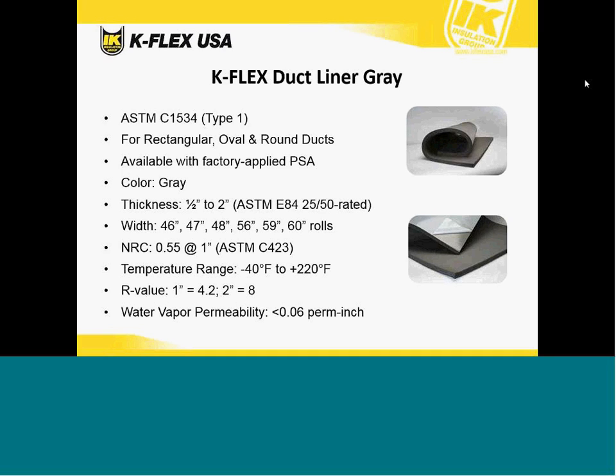The noise reduction coefficient is 0.55 at 1 inch, measured by ASTM C423. The temperature range for this product is from -40 Fahrenheit to +220. The R-value at 1 inch is 4.2, and at 2 inches is 8, which complies with most local codes. And the vapor permeability of this product is less than 0.06 perm-inch, which is below that ASHRAE Class 1 vapor retarder line.